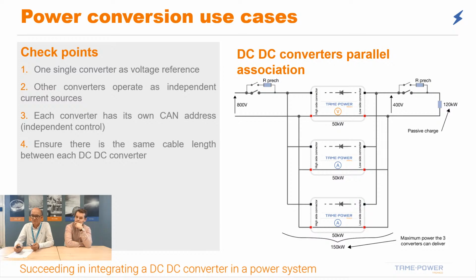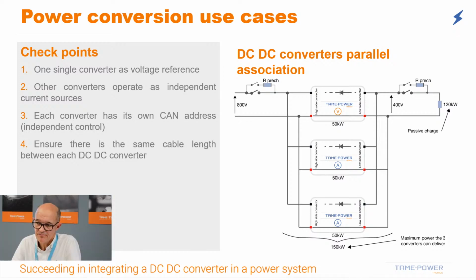One thing you should have in mind is the non-isolation inside the converter. This means all the 0-volt lines are all connected together. So in such a schematic, if one 0-volt line to one converter is really longer than all the others, that should unbalance the current in the 0-volt line and change the electrical behavior of the converter. So you should take care of the wire length and the wire resistive path on the 0-volt line to ensure a stable and balanced share of currents among all the 0-volt lines.